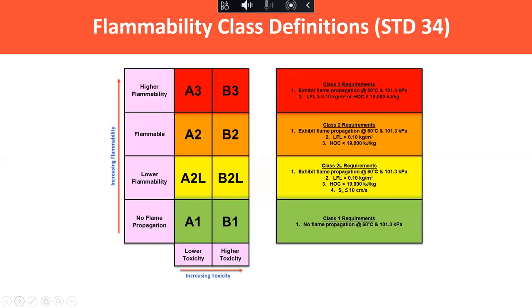Just want to ground everybody, if you're not totally familiar with flammable refrigerant definitions - this is right out of ASHRAE Standard 34. By and large, most refrigerants we're all familiar with working with over the last few decades have been what are classified as A1. The A or B designation refers to the toxicity, lower or higher toxicity, and then 1, 2, 2L, 3 is the flammability. So A1 would be things we're all familiar with: 404, 134A, 410A, etc. And then the 3s have been around, but in pretty limited use because they are the highly flammable, or almost explosive, refrigerants like propane and butane.